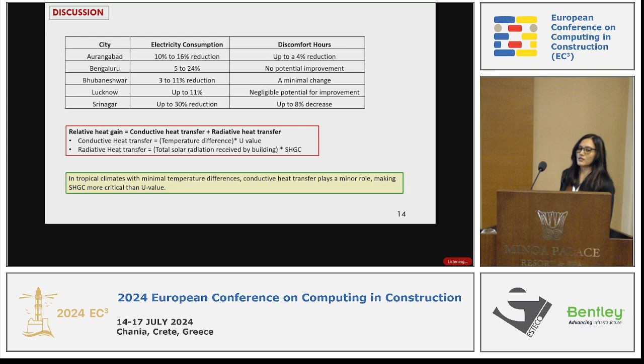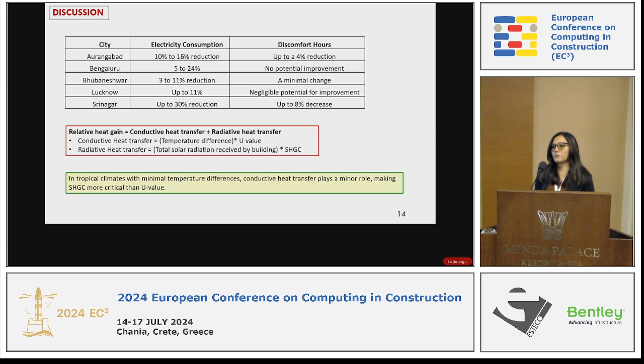So what we are concluding is that for the tropical climate in India, there is very little difference between the outdoor and the indoor environment within the buildings. The conductive heat transfer plays a minor role. Therefore, we can recommend glazing options with lower solar heat gain coefficient, and the U value is not playing a major role, so it can be put in a moderate range. So these are the conclusions which can be drawn from the study.